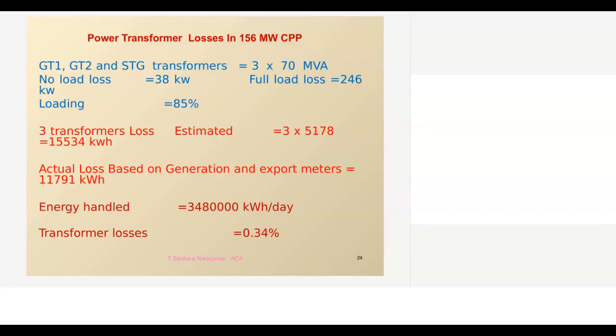See, we have done this for a transformer, because every time we tell theoretically that a transformer has low loss. This was taken for a combined cycle power plant. There are 2 generators, gas turbines, and 1 steam turbine. Each generator has a separate 70 MVA transformer, so there are 3 70 MVA transformers in operation. The no load loss of each 70 MVA transformer is 38 kilowatt. Full load loss is 246 kilowatt. Being a power plant, the loading is a maximum of 85%.